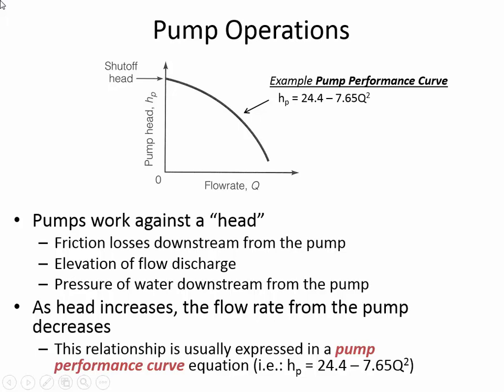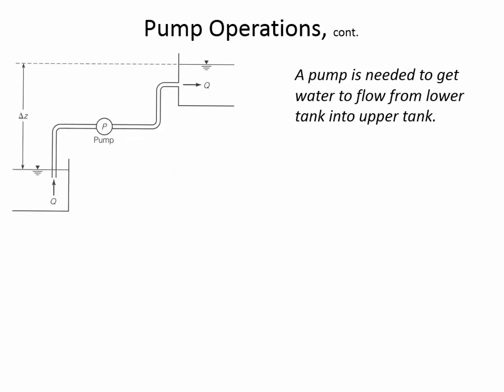And later on, as we go through an example, I'm going to tell you to set this pump curve equal to a system curve. You can solve it graphically or you can solve it numerically. To solve it numerically, you'll have to have it in this form, where HP is on the left side. You've got some intercept, the 24.4, which is just where the curve hit the y-axis, and then negative some C value, a coefficient that gives you the curve that's expected. We'll talk about that. Okay, so this is the pump curve. Here is how we create a system curve.